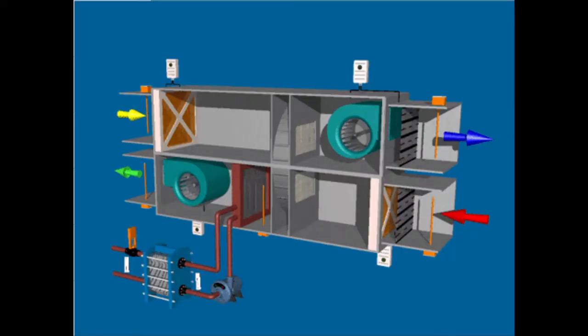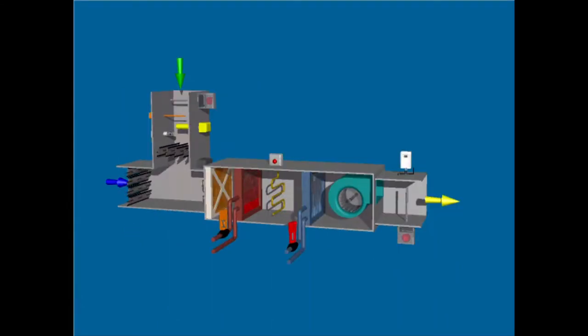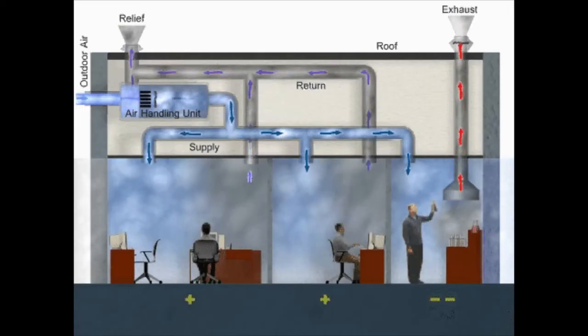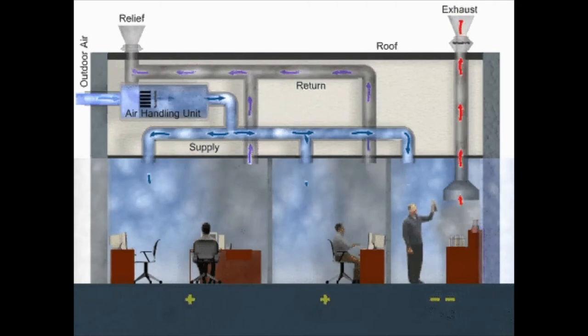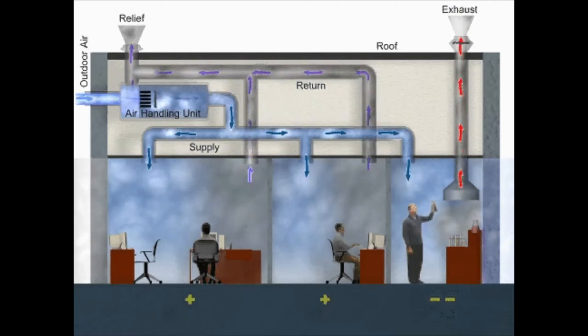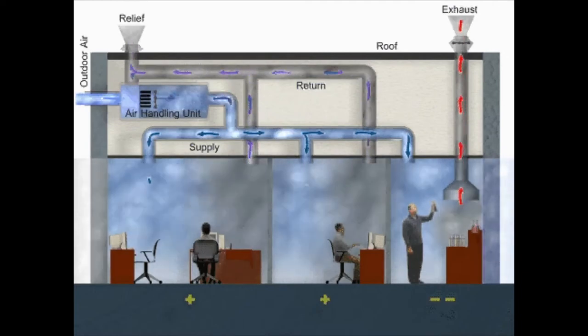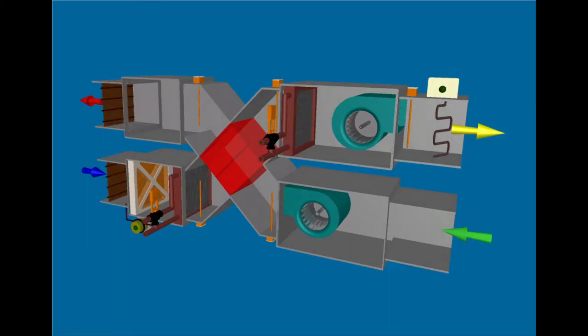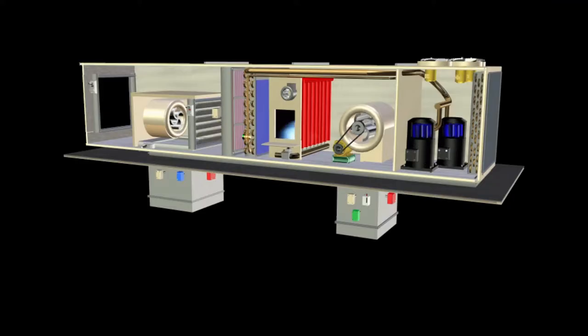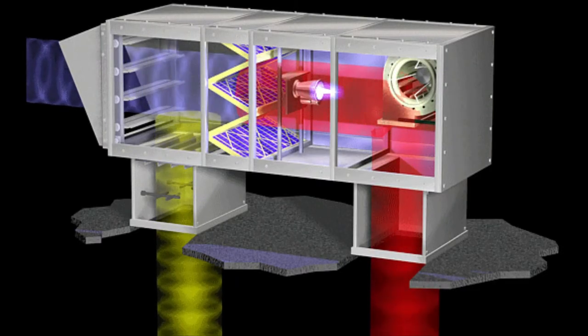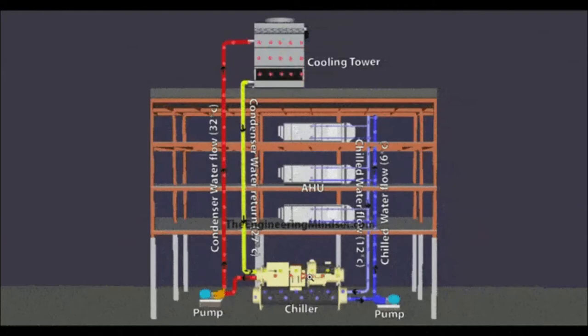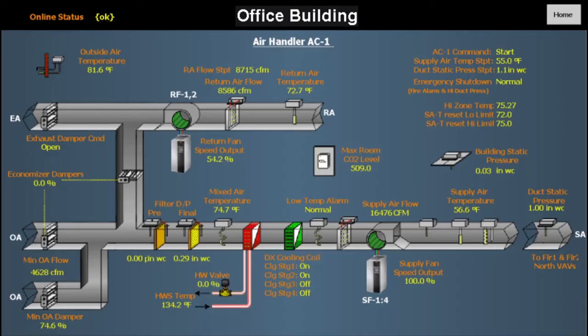So let's talk about air change. What is air change? Air change basically tells you how many times an hour you are, in an ideal situation, replacing that volume of air. Let's make the math easy: 6 air changes per hour. If you take 60 divided by 6, that means every 10 minutes you are replacing the air in your room with new air. So you can get an idea of what your turnover rate is. Turnover, air change per hour.